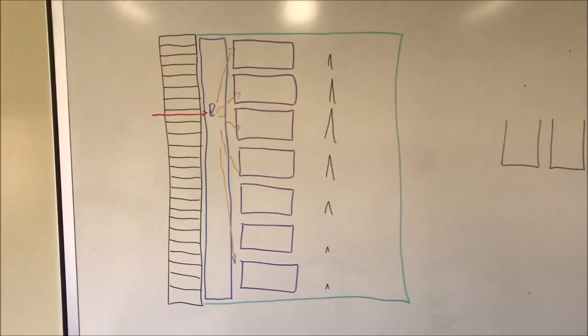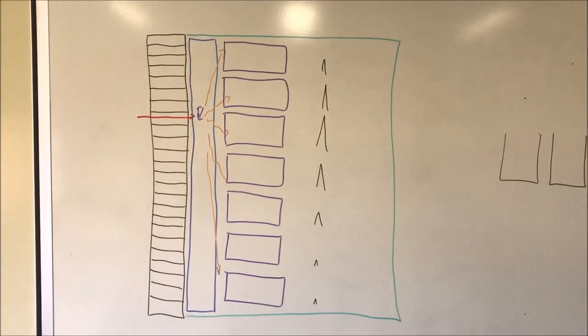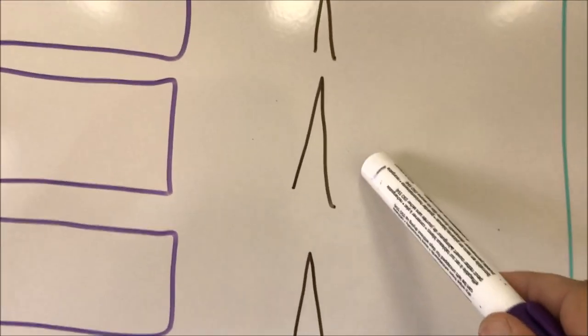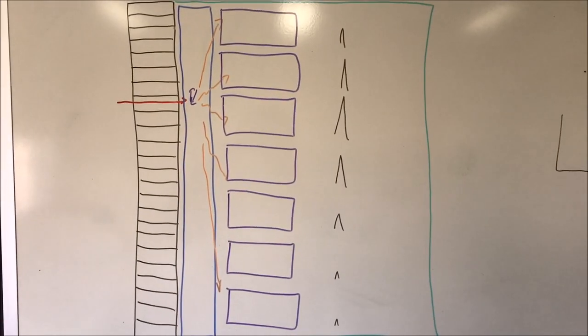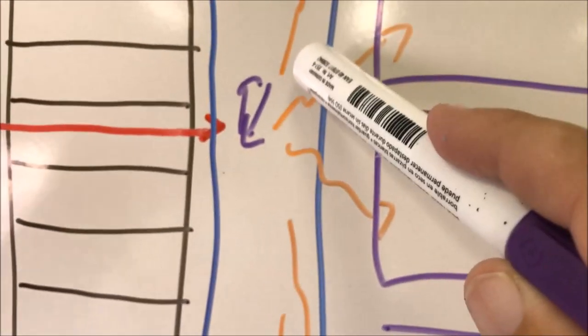Let's talk about what happens to those signals that come out. Even though they've been amplified through the PM tube, the amplitude of the signals will differ depending on how much light the PM tube detected. In this scenario where the event occurred here, the two PM tubes that are closest will end up with an amplitude higher than ones that are further away. The closer a PM tube is to the event, the higher the signal, so its amplitude will be slightly higher.